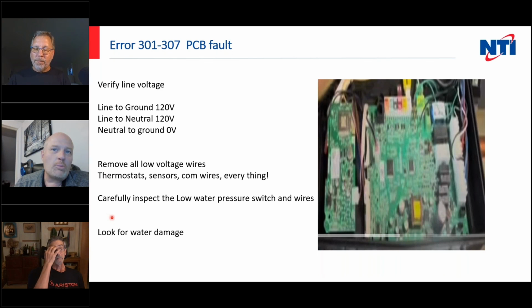Carefully inspect the low water pressure switch, and this is specifically to do with TRX FTVN boilers. If that pressure switch or the wires get wet or damaged, it very commonly causes a 303 error code, and once you dry the wires off, your boiler control is perfectly fine. You don't have an issue. Look for water damage, and of course, as soon as you get something wet, all bets are off.